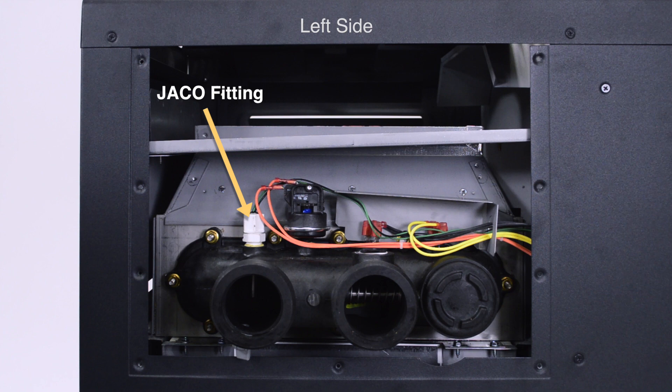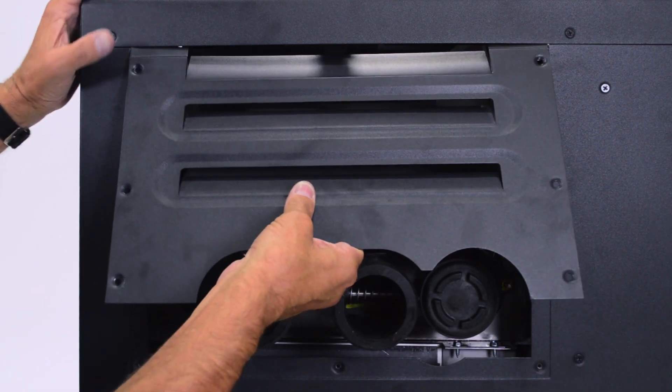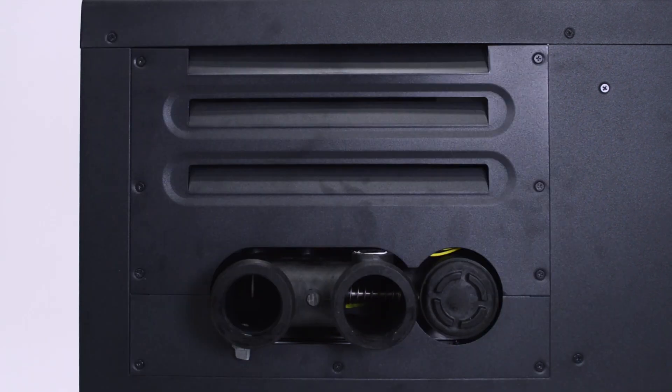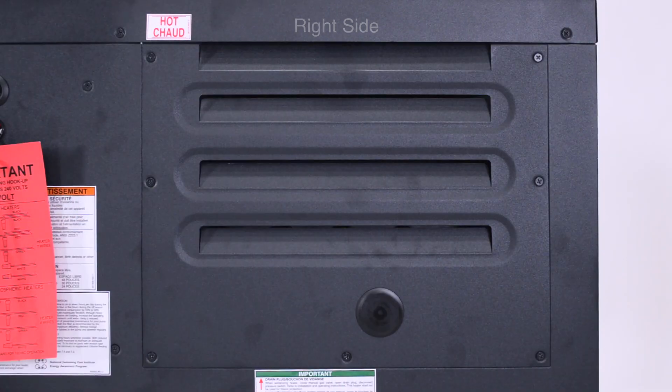Tighten the JACO fitting on the temperature sensor hand tight, then use a wrench and tighten one quarter turn more. The access panels must be reinstalled on the opposite side from their original location, aligning with the inlet-outlet header and return header's new configuration.